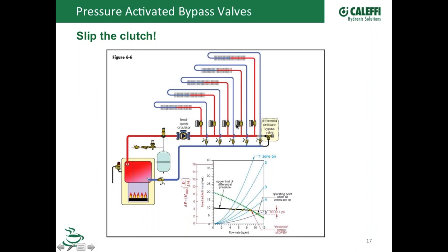Now, as the valves start closing off, this pump is still giving you a fixed output. So what the bypass valve allows to happen is that the excessive head energy being added, that you can't use out in the zones that are closing off, now just goes right back to the boiler. I kind of liken it to slipping the clutch. If you've got a vehicle with a standard transmission, when you first start out at the stop sign, you're giving a little bit of gas and you're slowly letting the clutch out until you get the car rolling and let the clutch all the way out. That's basically what's happening here: as the valves start closing, we're pushing that clutch pedal and then we're letting it slip a little bit of flow going back to it.